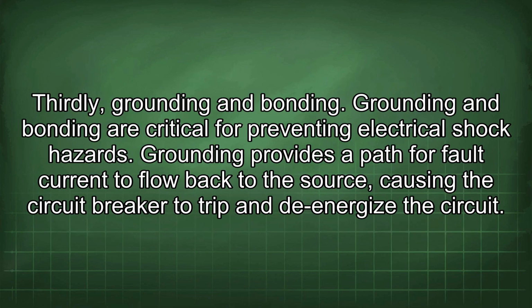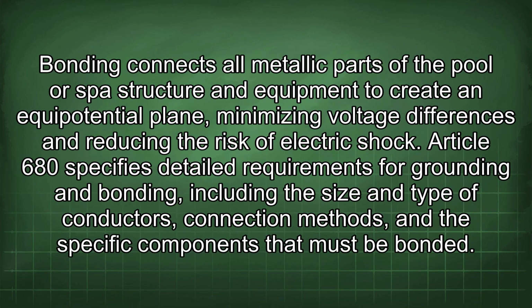Thirdly, grounding and bonding. Grounding and bonding are critical for preventing electrical shock hazards. Grounding provides a path for fault current to flow back to the source, causing the circuit breaker to trip and de-energize the circuit. Bonding connects all metallic parts of the pool or SPA structure and equipment to create an equipotential plane, minimizing voltage differences and reducing the risk of electric shock. Article 680 specifies detailed requirements for grounding and bonding, including the size and type of conductors, connection methods, and the specific components that must be bonded.